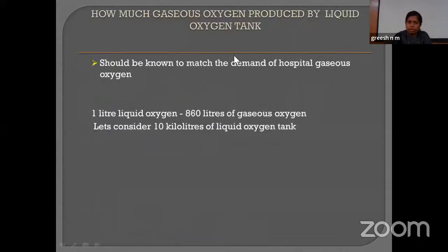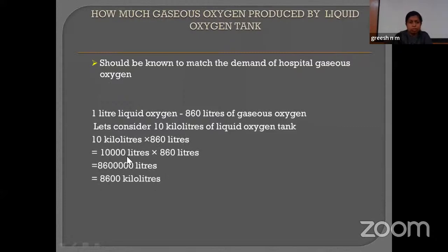How much gaseous oxygen will be produced by a liquid oxygen tank? We should know about it, because it has to ultimately match the demand of the hospital for gaseous oxygen. As we are all aware, 1 liter of liquid oxygen generates around 860 liters of gaseous oxygen. So let us consider a 10 kiloliter liquid oxygen tank. So 10 kiloliters into 860 liters, that is equal to 10,000 liters into 860 liters, which ultimately generates around 8,600 kiloliters of gaseous oxygen.